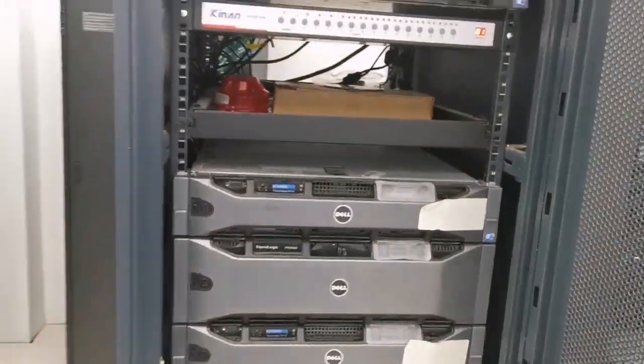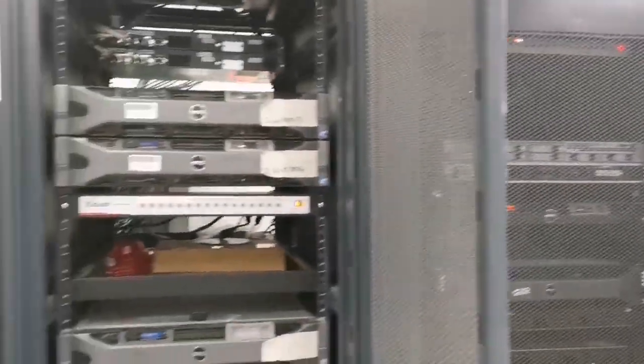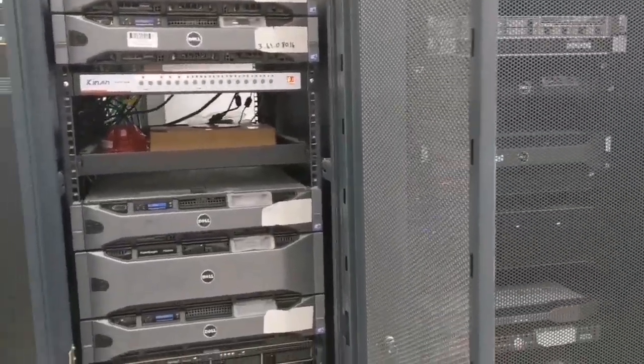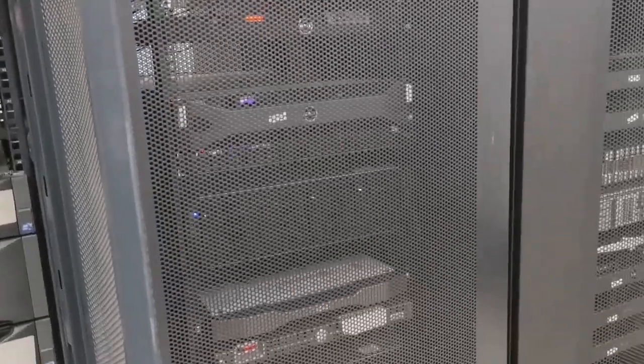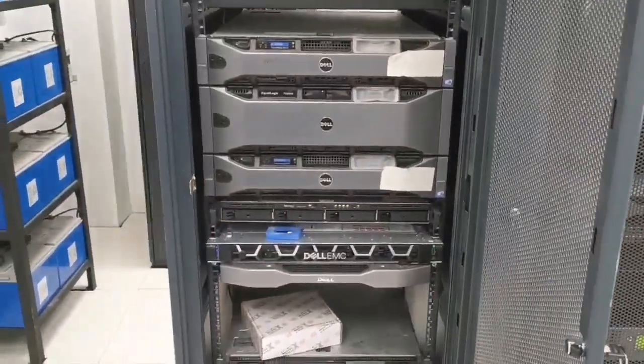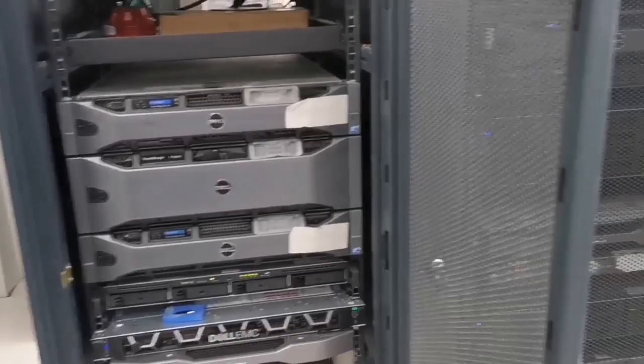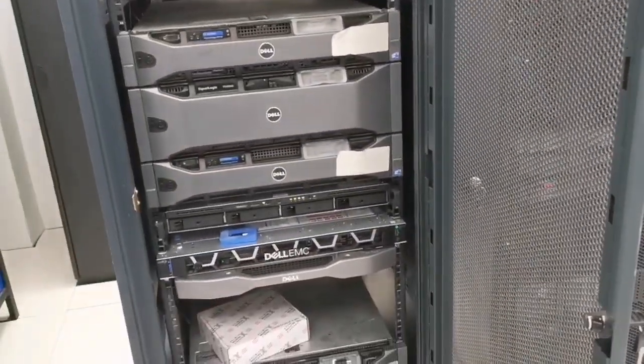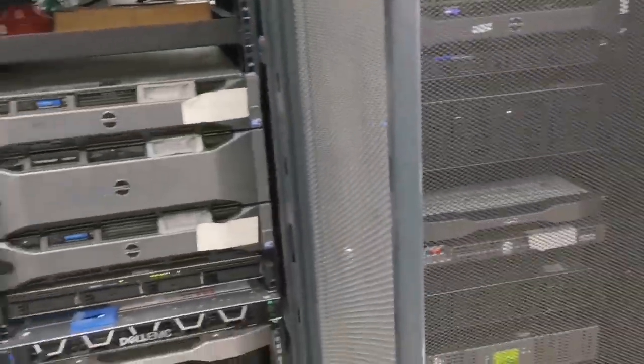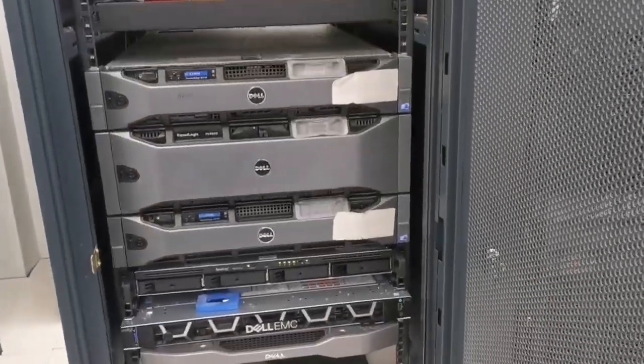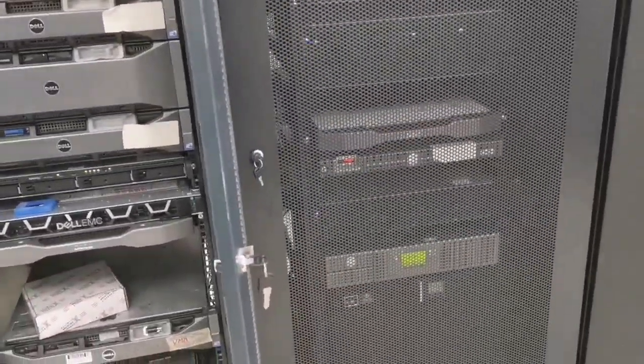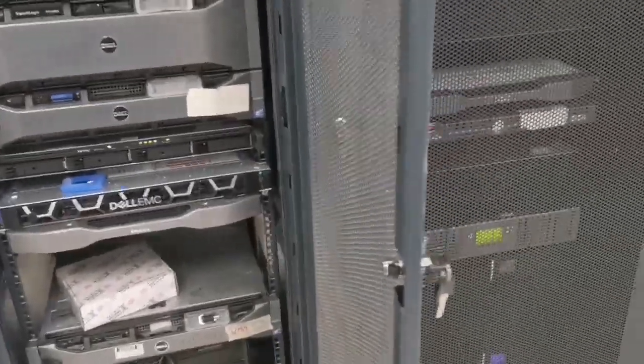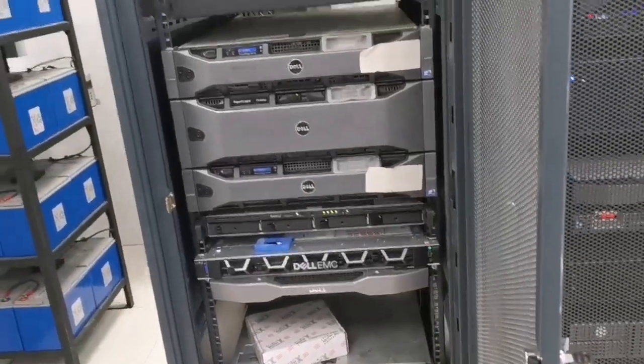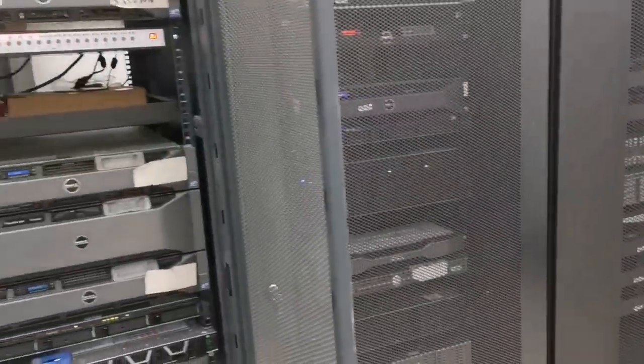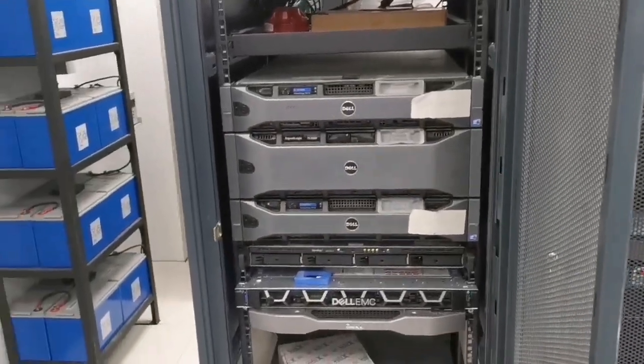Cabinets may come smaller than 42U, but usually inside the server room we use 42U cabinets from the beginning in order to be able to grow with the servers and install more equipment without the need to change the cabinet itself. Because when you want to change the cabinet, you have to turn off your equipment, your server, your storage, and then move it out of the cabinet and into the new cabinet, which will cost you downtime, something that you don't want to have in your server room.